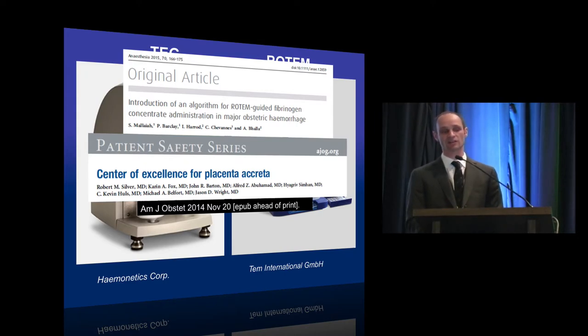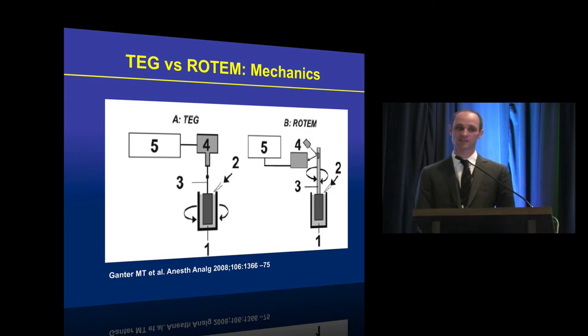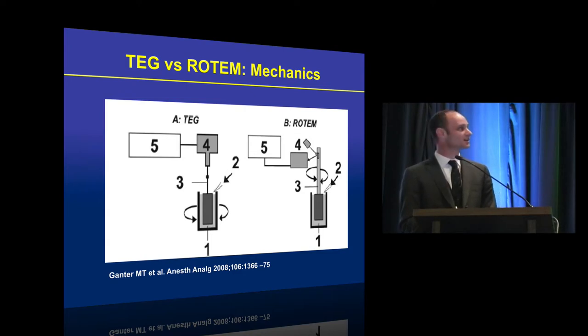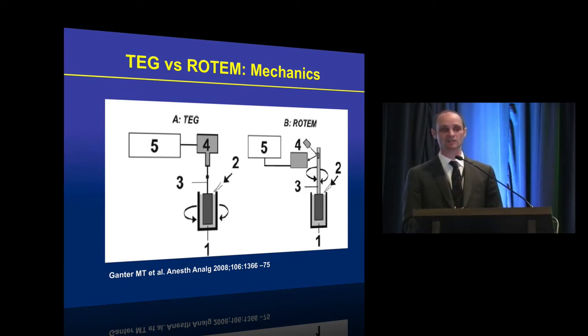How do they work? With TEG, you take a sample of blood from the patient and place it in a plastic cup, which is placed on a platform in the device. A pin attached to a torsion wire is inserted into the well of the cup. The cup rotates through a very small angle, and clot starts to form between the inner wall of the cup and the pin. This creates torque on the pin, detected by an electromechanical transducer system, which converts the signal into an electrical signal shown as a trace on a computer screen.